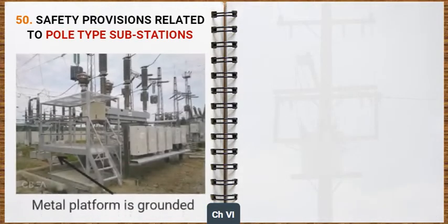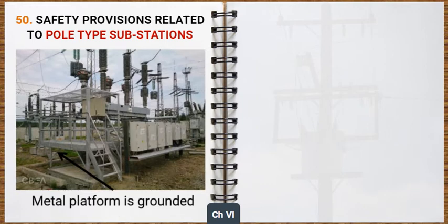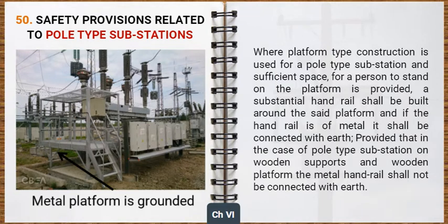Next, we will learn about the safety provisions related to pole-type substations. Where platform-type construction is used for a pole-type substation and sufficient space for a person to stand on the platform is provided, a substantial handrail shall be built around the said platform, and if the handrail is of metal, it shall be connected with earth, provided that in the case of pole-type substation on wooden supports and wooden platform, the metal handrail shall not be connected with earth.